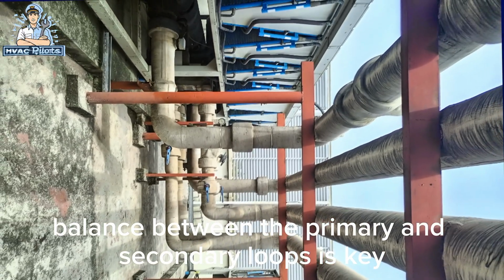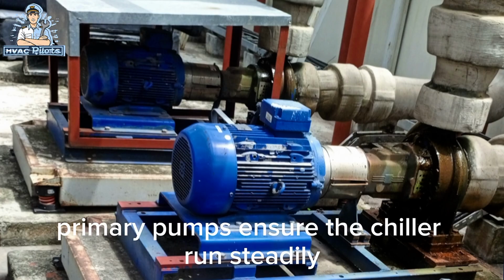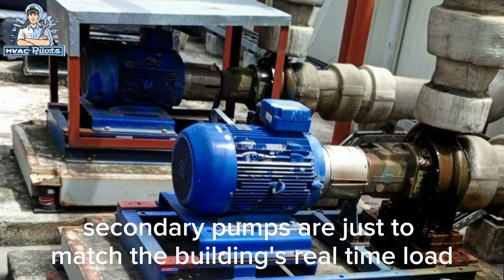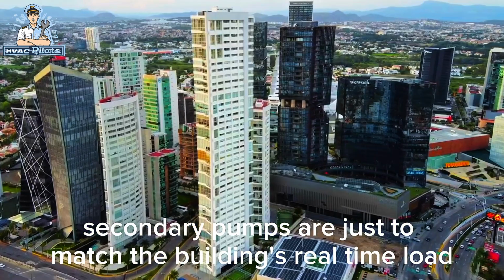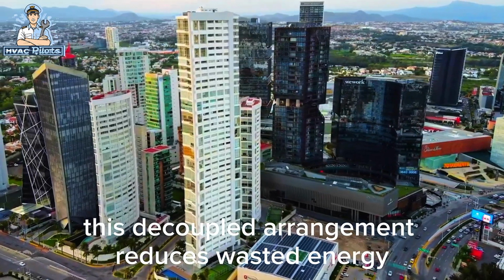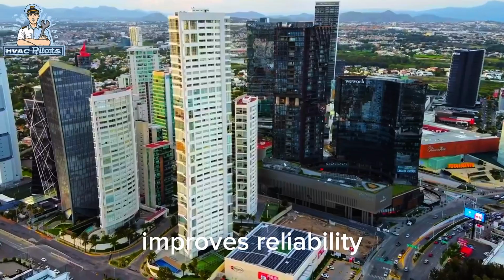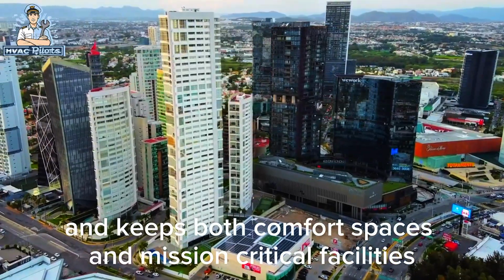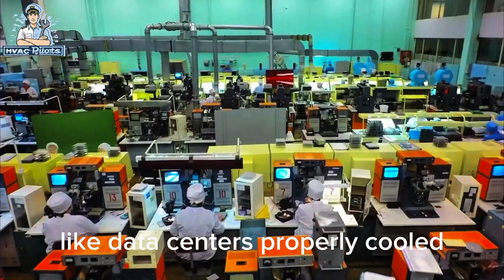For efficient operation, balance between the primary and secondary loops is key. Primary pumps ensure the chiller runs steadily. Secondary pumps adjust to match the building's real-time load. This decoupled arrangement reduces wasted energy, improves reliability, and keeps both comfort spaces and mission-critical facilities like data centers properly cooled.